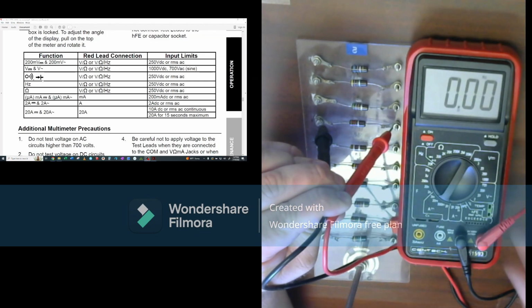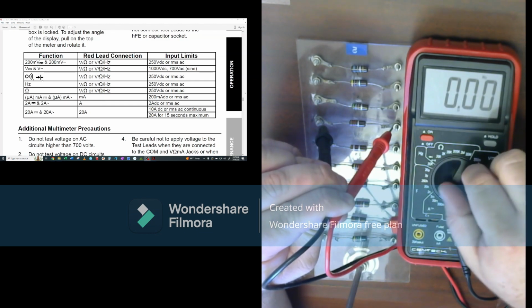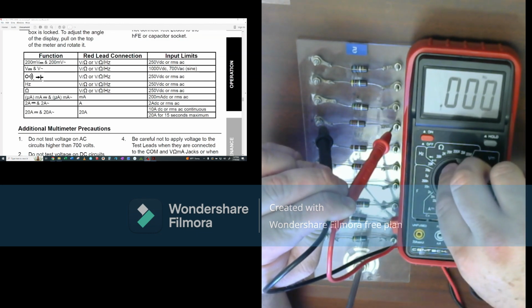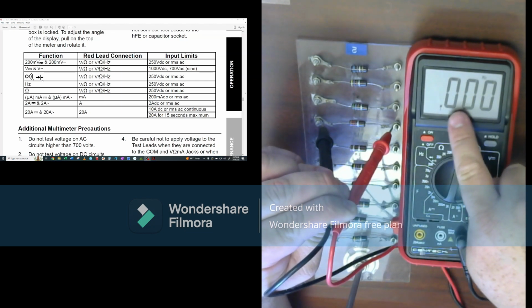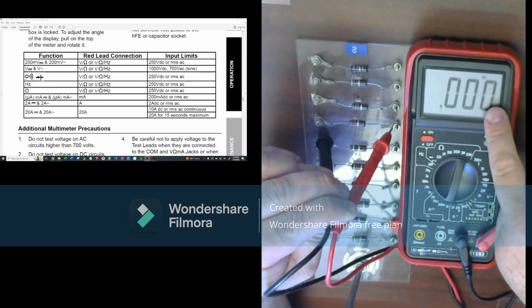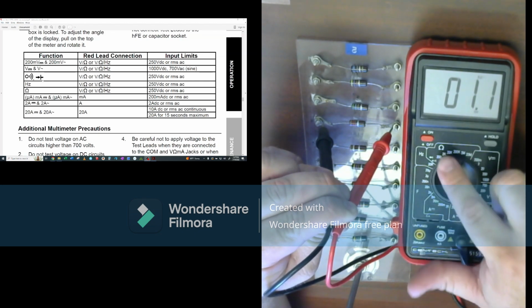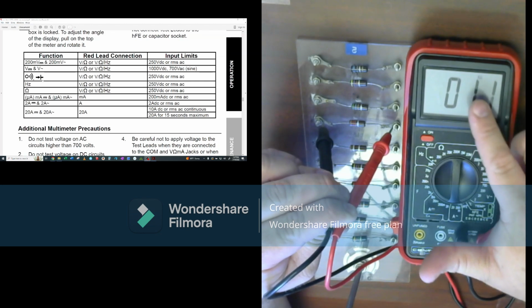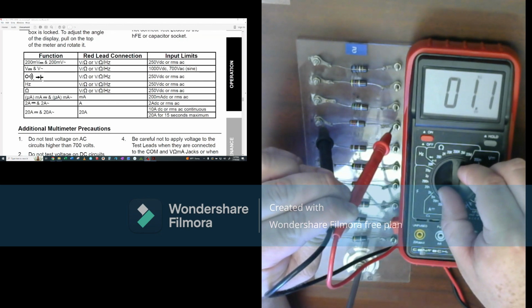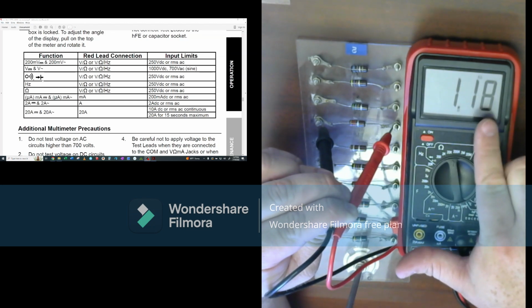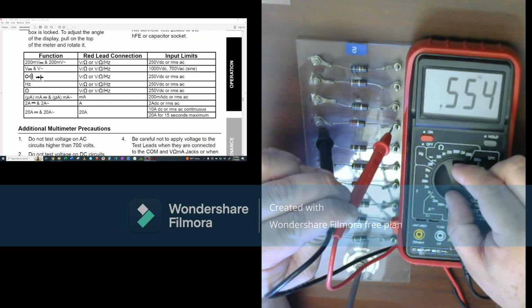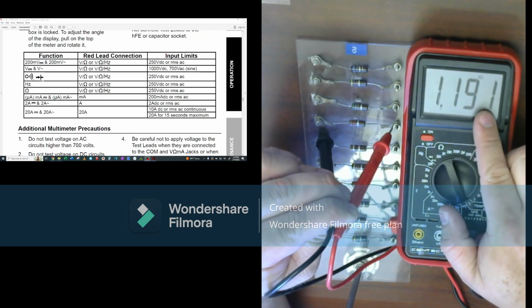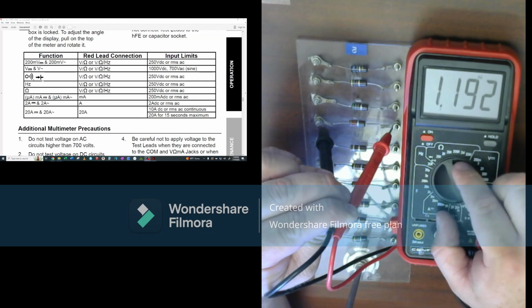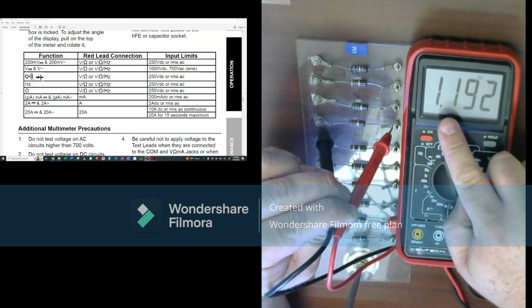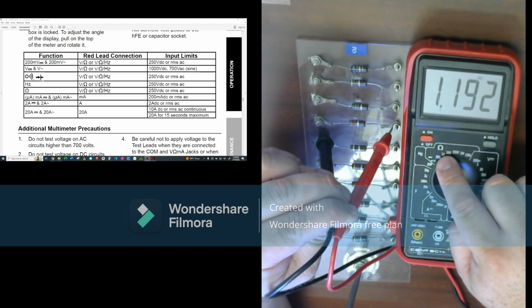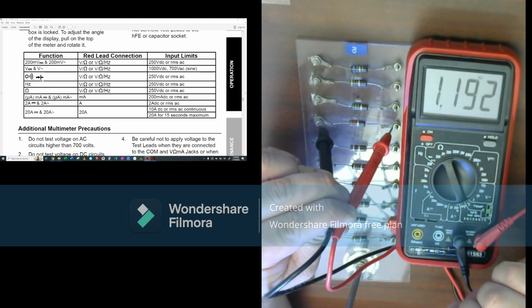So I'll hold those on there and use my hand. Now 20 meg is too large, we're not seeing anything, so I'm going to go down to 2 meg. Okay, that gave me an extra decimal, so it moved my decimal point over, but I'm still not fully reading it. I'm going to go down to 200K. Oh look, now I'm starting to get a measurement, but now I only have 1.1 kiloohms versus megohms. Let's go to 20K, that gives me my 1.18, so we're getting closer. And if I go to my 2K, that gives me 1.19 with my last digits, so we can kind of sneak it in. And at 2K, we know we're reading 1.1K, 1.2K, the maximum is 2K, we're probably pretty good and don't need to drop down another level.